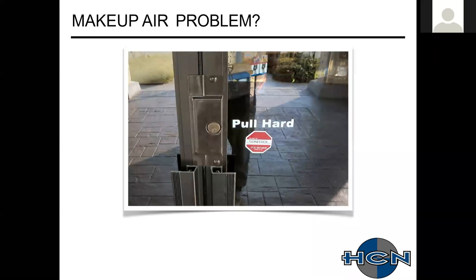So if air doesn't come in to replace what goes out through the hood, you're going to have problems. I'm sure a lot of people have walked up to a restaurant somewhere where they're pulling hard on that door. There's definitely a negative pressure issue here.